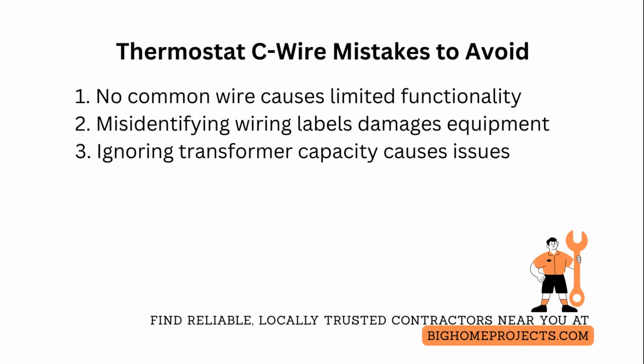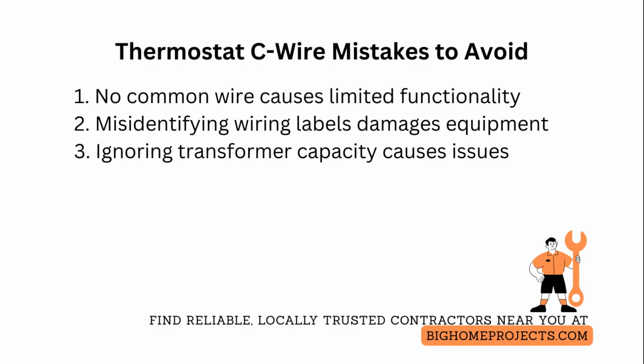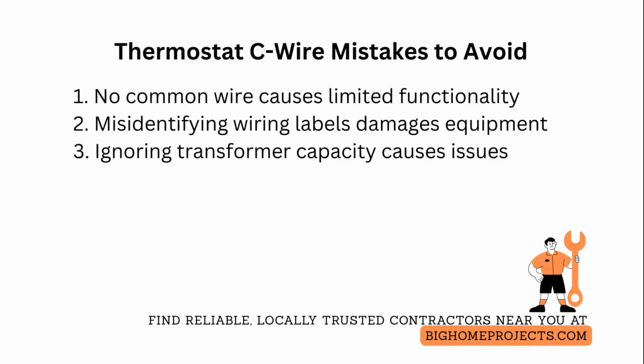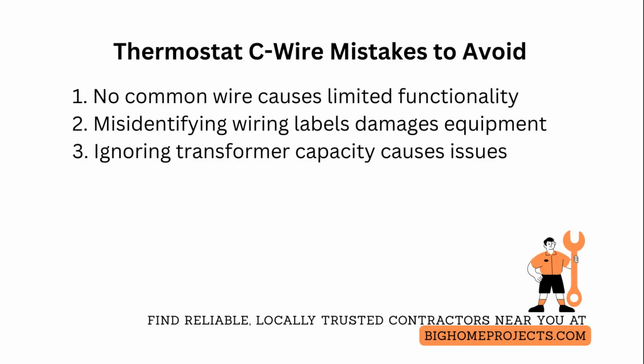The second frequent issue is misidentifying wiring labels. Using the wrong terminal for heat, fan, or compressor can damage equipment. Fix this by tracing each conductor to the control board, measuring continuity, and consulting the equipment wiring diagram before connecting.